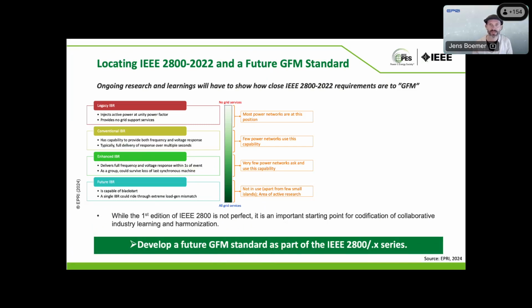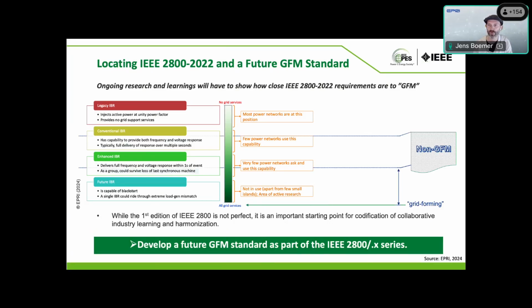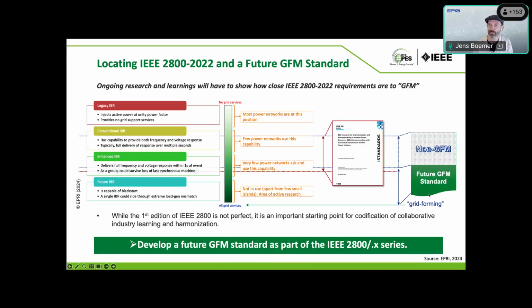Now, one question is related to the grid forming standard, how that can actually become complementary to IEEE 2800. Because to some extent, IEEE 2800 may already stretch into performance requirements that are related to grid forming equipment. But there's still this gap, and the new project is meant to fill the gap from whatever 2800 right now provides in order to increase the share of inverter-based resources all the way to true grid forming capability, which the working group will have to figure out what that actually means.